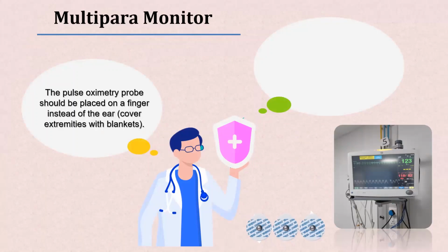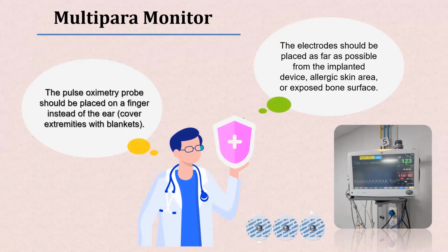The pulse oximetry probe should be placed on a finger instead of the ear, and the extremity should be covered with blankets to keep it warm. The electrodes should be placed as far as possible from the implanted device, allergic skin area, or exposed bone surface.